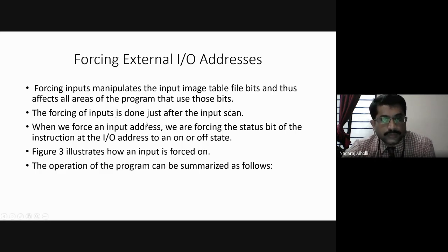The forcing of inputs is done just after the input scan. Once we are doing the input scanning process, just after the input scan, suppose there is one more scanning process you want to carry out. After the first scanning process, whatever data we manipulate by forcing the input or output device will be reflected into the input image table file or into the output image table file.